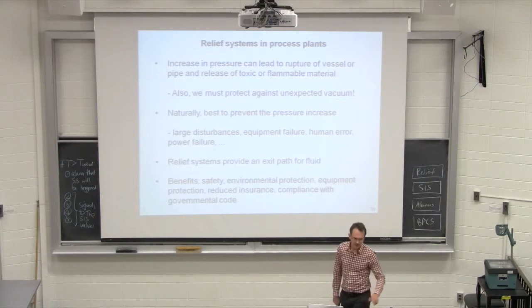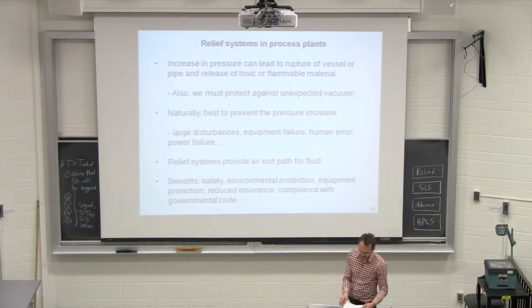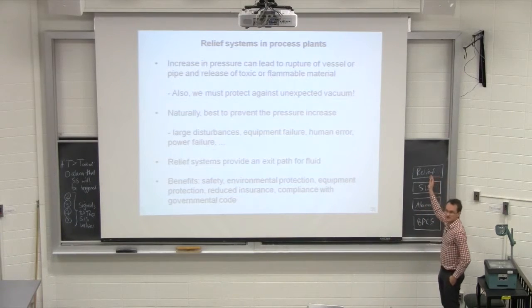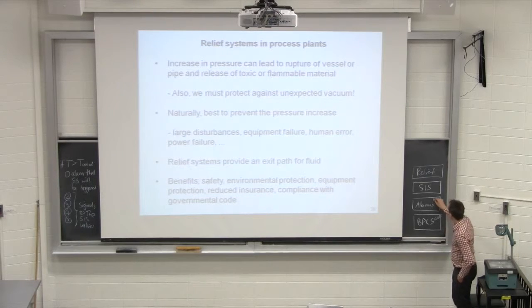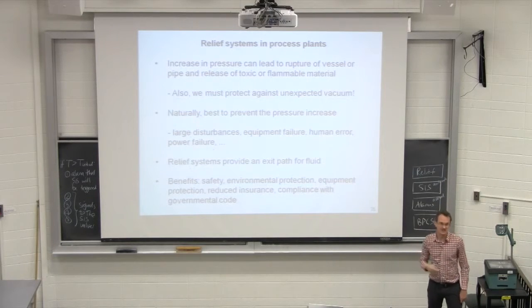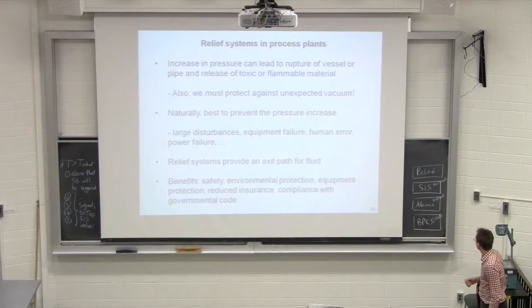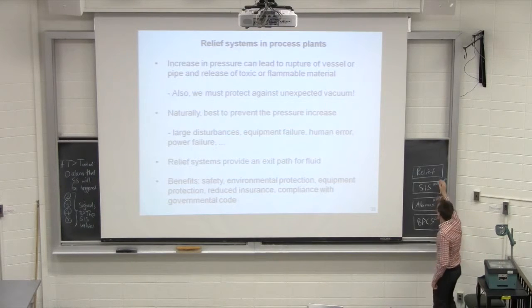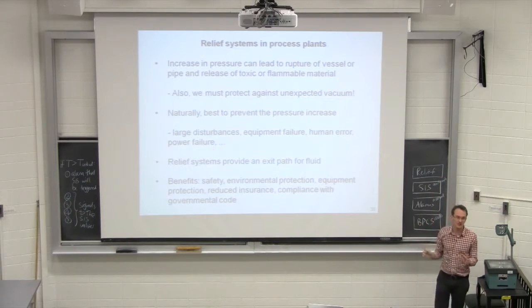Okay, so where we're headed next is, as I mentioned, we're going to now consider this idea of relief. Now, relief is really a last resort. We've gone through a layer here that's automatic. Here we've gone through a layer that's manual, with the operators trying to fix the process. Here we've gone through a layer that's automatic, an instrumented system that will automatically try to bring the process to a safe operation point. Now we're really at the last resort. This is the last thing we're going to try.